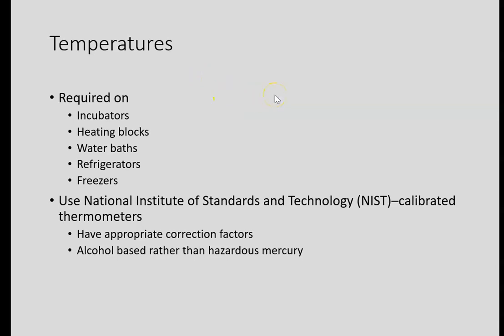In microbiology, we also took not just room temperature but also room humidity level, because the humidity level could affect some of the testing that we did at bench. The National Institute of Standards and Technology provides thermometers that are calibrated by the institute, with correction factors and things that you need to follow. The red or blue liquid inside has replaced the silver or mercury.